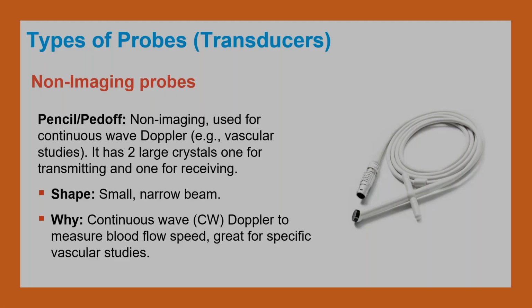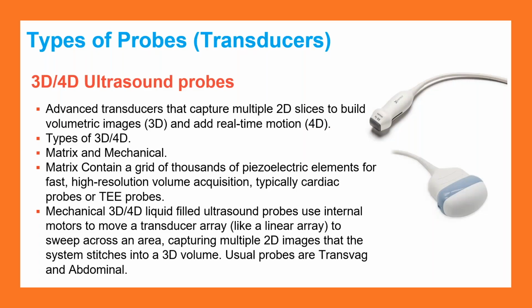3D, 4D probes again, there are different types. There's mechanical ones, and there's what they call matrix array ones that don't have any moving parts in them. Their image quality is amazing, but they're also very expensive. So the sooner you can detect a problem with a 3D, 4D probe and get it in for evaluation, the better it is for you, because on a mechanical one, if all the fluid leaks out of it, you're going to get an image quality problem because there's air where there should be fluid.